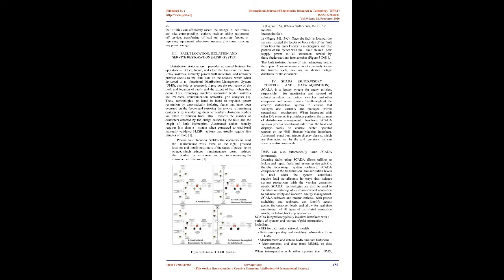Automated feeder monitors. Feeder monitors measure the load on distribution lines and equipment and can trigger alarms when equipment or line loadings start to approach potentially damaging levels. Monitors deliver data in real time back to the systems, so that utilities can efficiently assess the change in load trends and take corresponding actions, such as taking equipment off service, transferring load to a substitute feeder, or repairing equipment whenever necessary without causing any power outage.